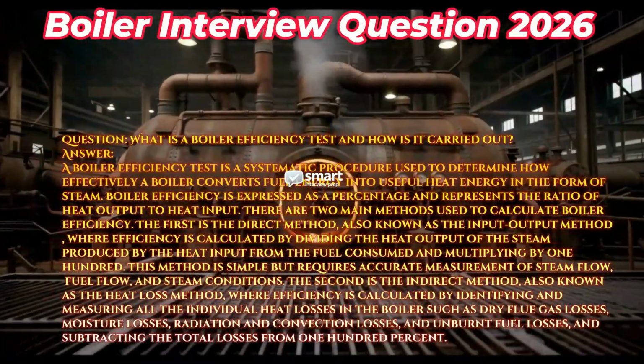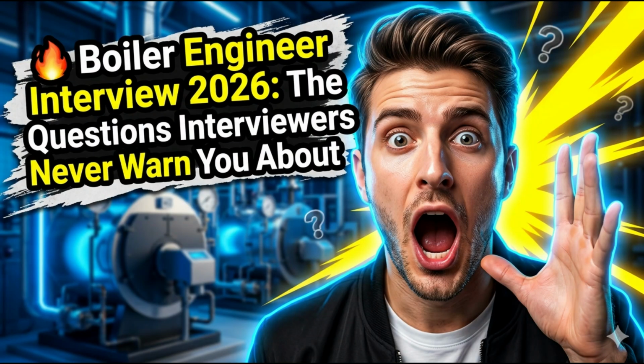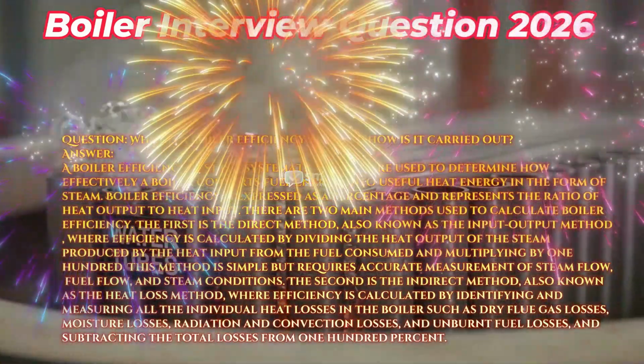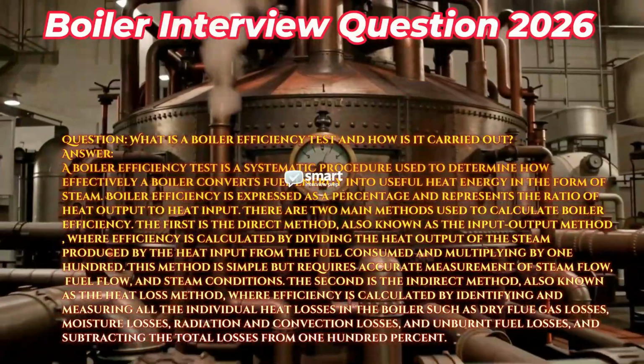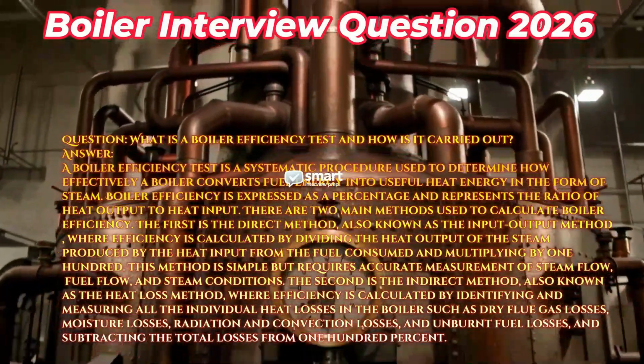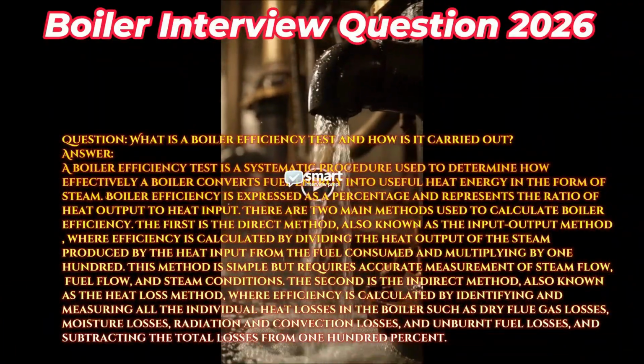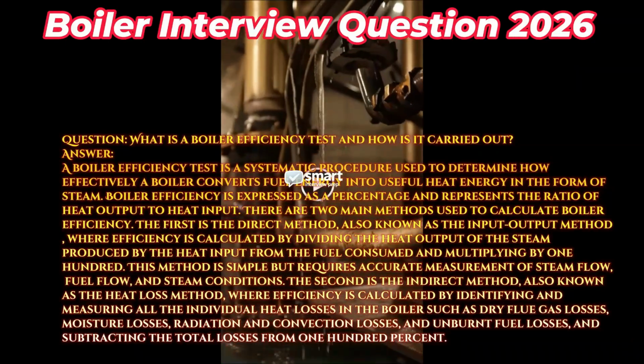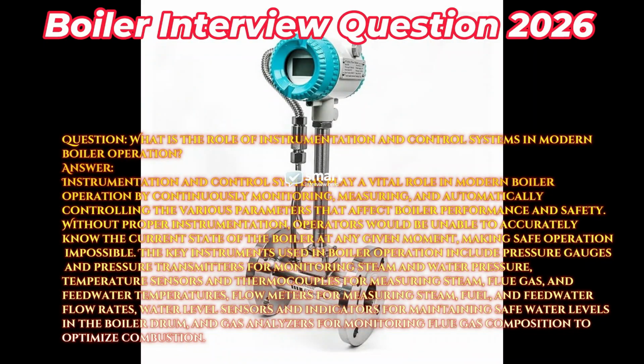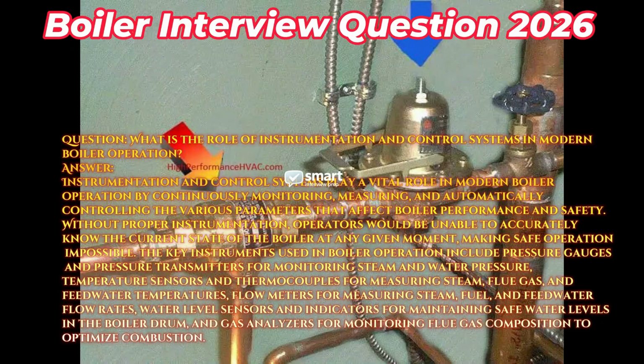The second is the indirect method, also known as the heat loss method, where efficiency is calculated by identifying and measuring all the individual heat losses in the boiler, such as dry flue gas losses, moisture losses, radiation and convection losses, and unburnt fuel losses, and subtracting the total losses from 100%. Question: what is the role of instrumentation and control systems in modern boiler operation?